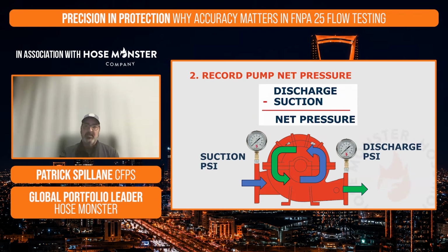So we're going to look at our gauges on each side of the fire pump. We're going to look at our discharge side of the fire pump, and we're going to document and record that pressure. And then we're also going to record our suction pressure of the fire pump. And then we're going to do a little math. We can do it after the test. We don't have to do it in the middle of the test. But we're going to subtract those numbers from each other. So discharge minus suction, and that's going to equal our net pressure. That's the pressure that fire pump is adding to the water that's coming into it.